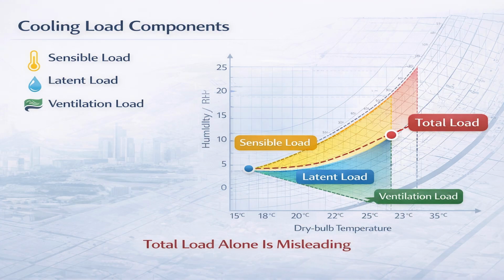When this breakdown is ignored and selection is based only on total tonnage, the result is predictable. The system may meet the calculated load on paper, but it struggles to control humidity, comfort, or energy consumption in reality. This is one of the most common reasons why HVAC systems that are fully approved still fail to perform as expected.